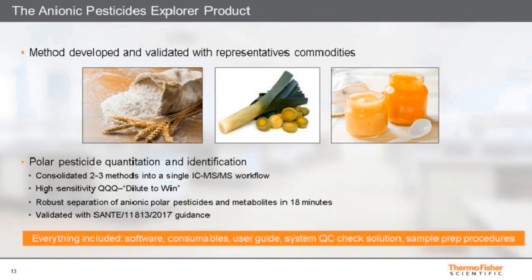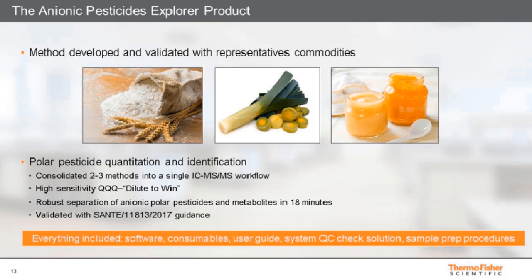The method was developed with representative commodities: wheat flour as an example of a dry commodity, leek for high pigment content, and baby food fruit-based as an example of a challenging matrix. All validation was done using European SANTE regulatory guidelines. The method consolidates the determination of polar and ionic pesticides into a single analysis, increasing productivity and reducing cost. The workflow is provided with a system suitability check standard, and the software includes preloaded acquisition methods, data processing, and reporting templates. For the triple-quad MS, all SRM transitions are optimized and preloaded into the software with relative collision energies and other MS parameters. The system also includes a detailed deployment guide for fast implementation and ongoing optimum performance.